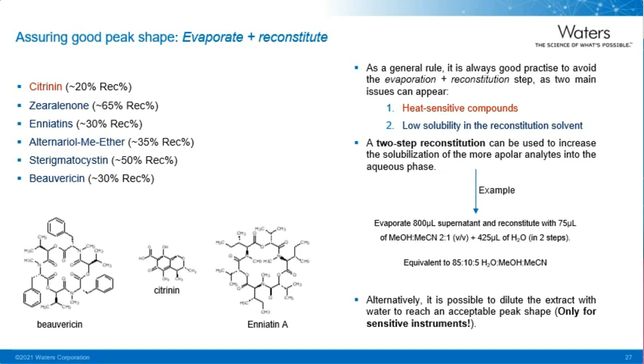Alternatively, if we have an instrument sensitive enough, we can dilute the extract instead of doing this reconstitution step. The problem is that not always we have the most sensitive instruments available, and we cannot afford to dilute the sample as much as we want because we start to lose the peak. In this case, we can still figure out a few strategies. Here I show 3 chromatograms of the same sample, an organic extract diluted 5 times with water and analyzed on a TQS micro using an FTN autosampler.